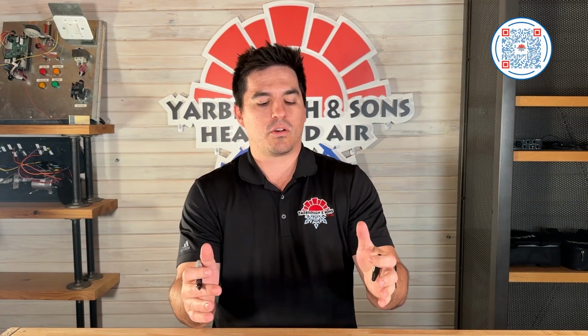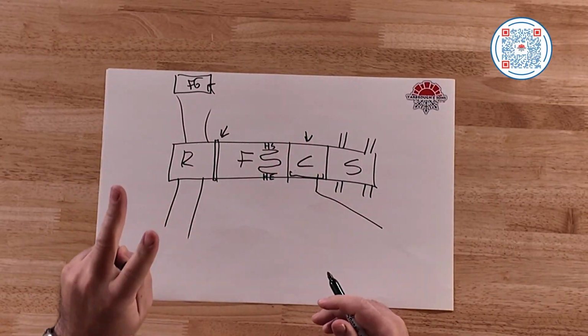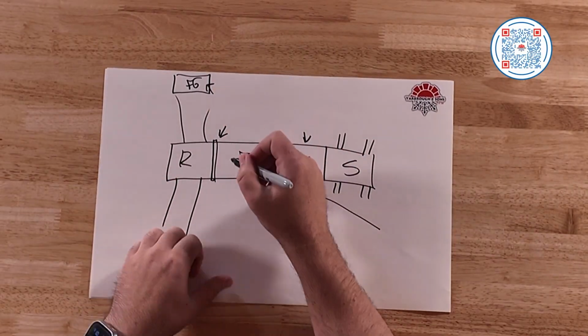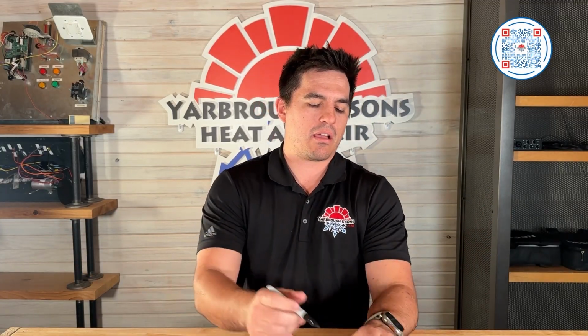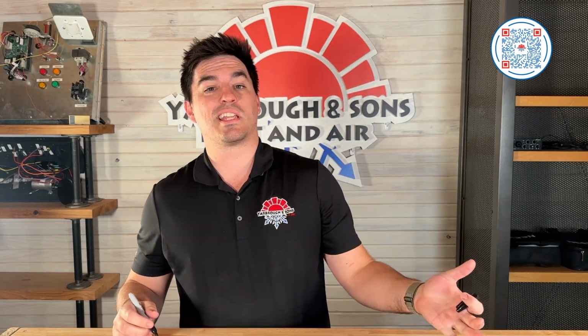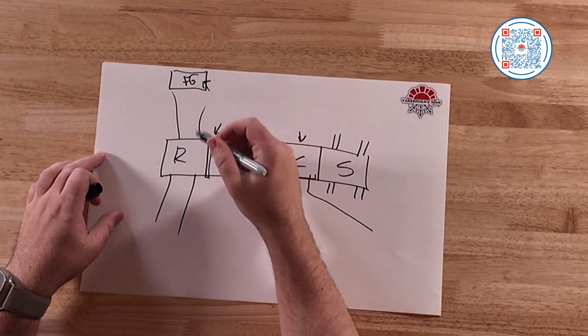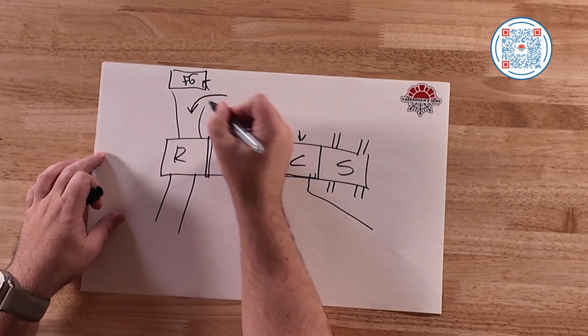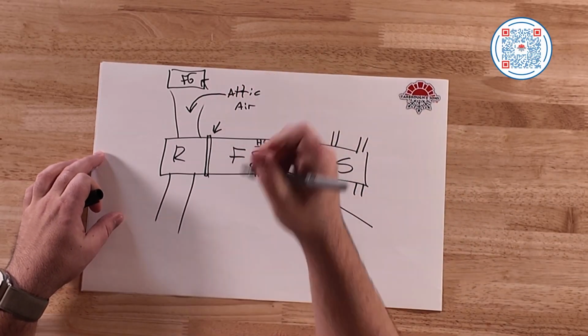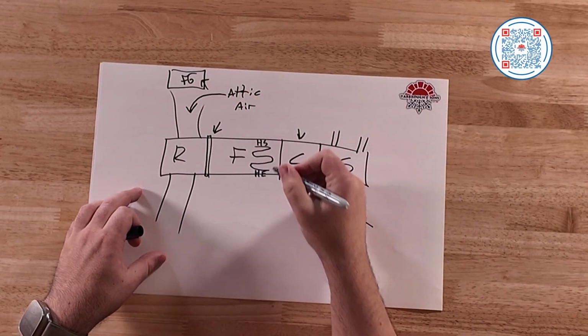Now you might say, well, I change my filters regularly and still experience those smells. Okay, there are some situations - let's say you've got filters in the ceiling. This goes back to the two different approaches: do I filter it in the ceiling or before the unit? If it's still smelling smelly, I'd make sure your ductwork is properly sealed, because there have been instances where you're changing filters regularly, but your ductwork is disconnected up in the attic space - barely connected - so air is passing from your attic space. That unfiltered attic air is making its way into the system.